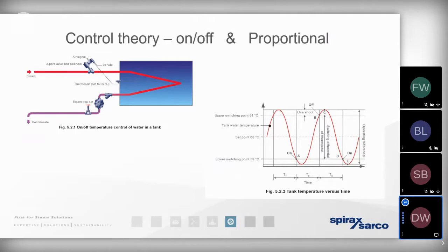So using the analogy of the light switch, it's a little bit like moving away from the on-off switch to a dimmer switch. It means it's cheap, it's simple, it's easy to engineer, but it's not ideal, as you can see from the little graph in the bottom right of the screen, because certain processes may not be able to live with that 2-degree overshoot, meaning that we get a slightly inconsistent temperature and that the valve could be in a position where it's constantly fighting itself. So that's typically available within self-acting controls.